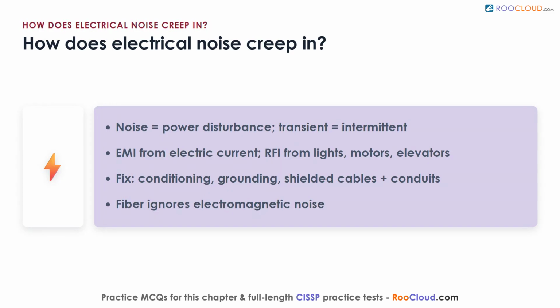Electromagnetic interference is generated by electric current and can corrupt transmissions on phone, network, and radio links. Radio frequency interference comes from everyday devices like fluorescent lights, motors, elevators, and space heaters, and it disrupts many of the same systems. You fight both by conditioning the power, grounding properly, using shielded cables and conduits, and switching sensitive links to fiber, which simply does not care about electromagnetic noise. Locate the noisy equipment first, then route your cabling to stay clear of it.